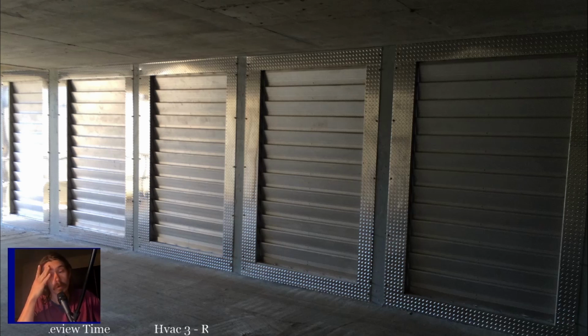Then you can have reverse acting, where as the temperature goes up, the pressure goes down, and then that valve closes more. And you may want that if your valves normally open the other way, or normally close the other way. So you might want it to reverse act if that valve's normally closed and you want it to open up, or whatever the case may be. So just remember there's direct acting and reverse acting thermostats. And a lot of times with pneumatics, what you need is pretty important because it's going to change how those valves open and close. Again, I'm trying to think of a situation where a pneumatic wasn't a chilled or hot water hydronic system, and I can't think of one. Doesn't mean they're not there, but it was a good way to control valves more than anything else and modulate valves. So that's typically what you're going to see if you're dealing with pneumatics.